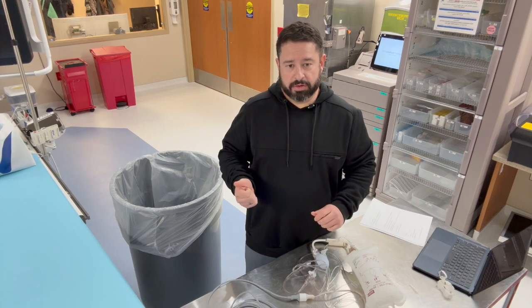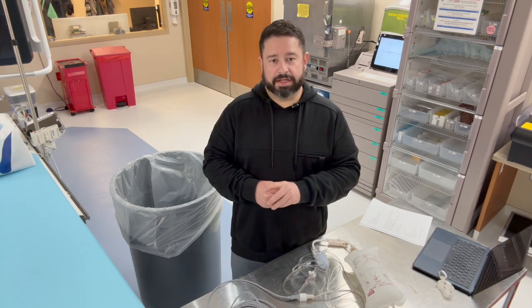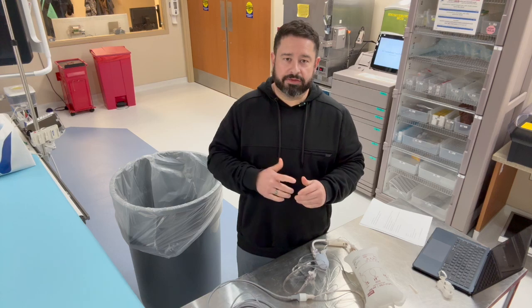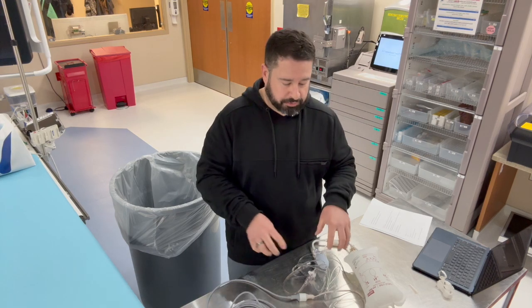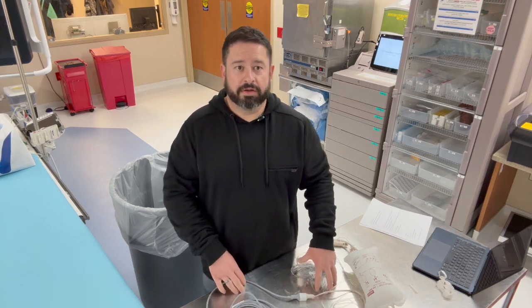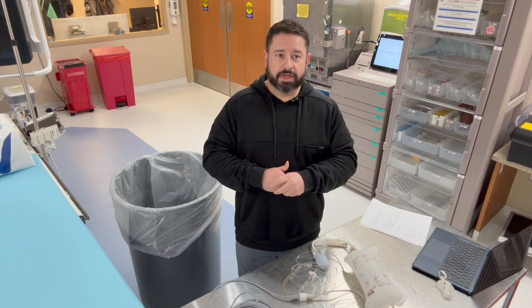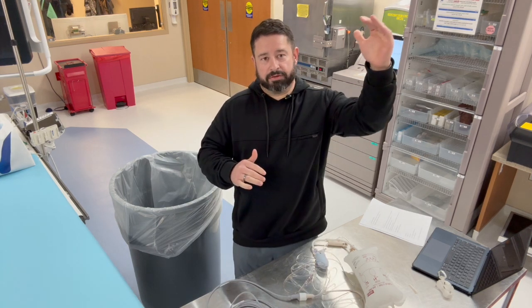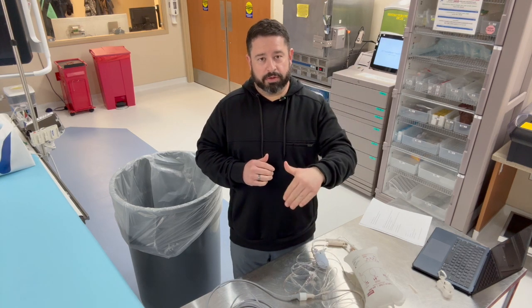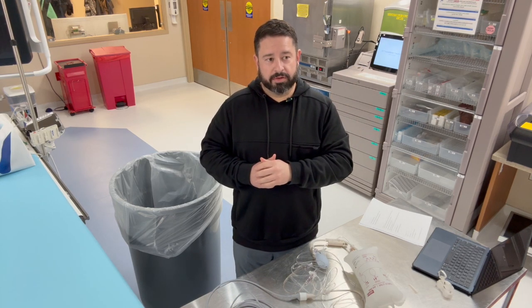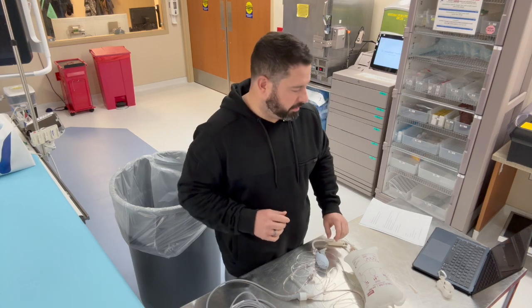So anytime you need to 0, anytime that you disconnect or reconnect that cable, you're going to have to 0. If you're doing this in flight, anytime you get to altitude, it's best to 0. Remember, you're zeroing this to atmospheric air, and when we're at ground level, it's fine. But when you get to altitude, you want to re-0. And then remember when you come back down to ground level, when you land, you want to re-0 it again.